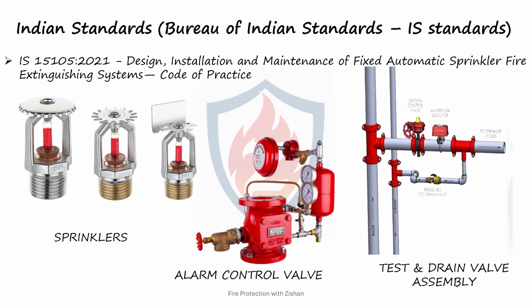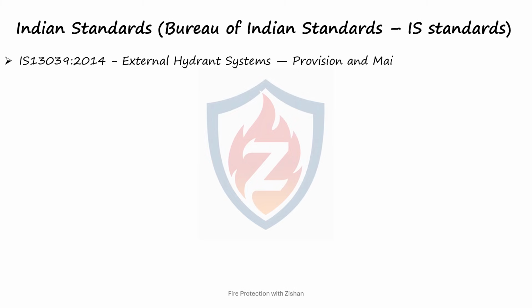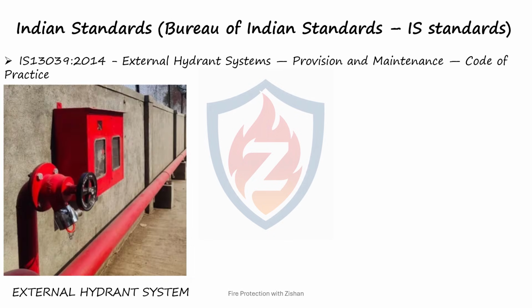Now, let's move on to another important Indian standard for fire protection systems, IS 13039:2014, which covers the requirements for external hydrant systems. This standard provides guidelines for the provision, installation, inspection, testing, and maintenance of external fire hydrant systems used for firefighting operations. As shown on the left, the external hydrant system consists of a network of underground and above-ground pipelines connected to fire hydrants strategically located around a facility. These hydrants provide a reliable water source for firefighting during emergencies.